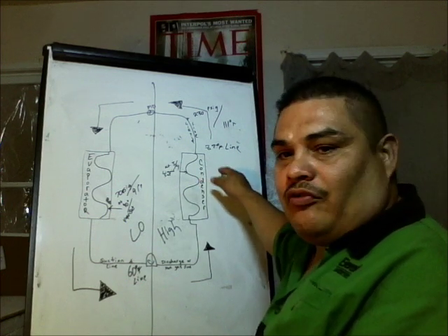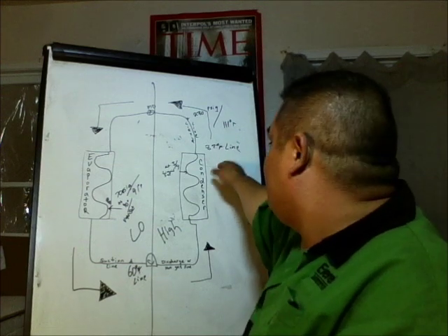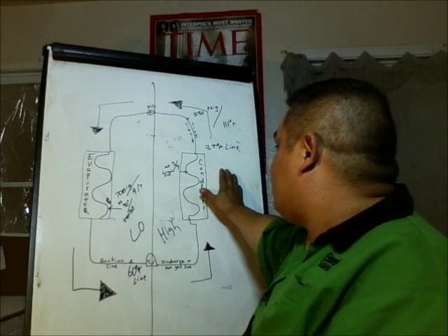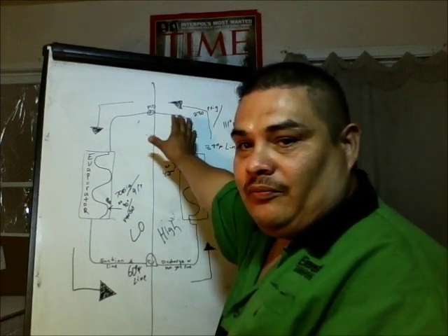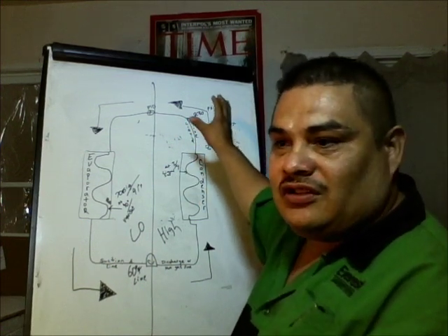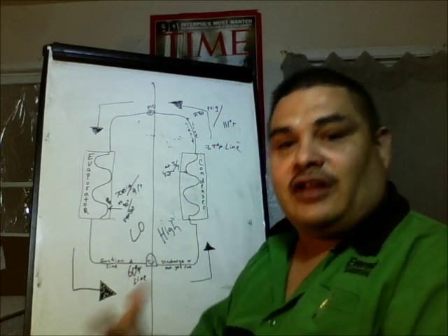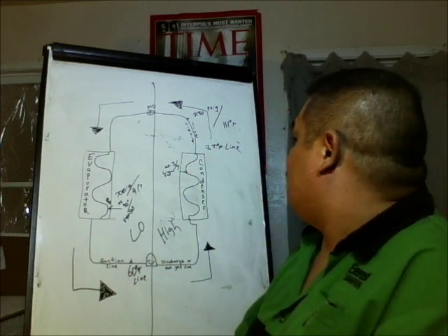You hit the point where it's complete liquid going out. That's a door where you're entering into subcooling. And that, again, is going out of latent heat and entering into sensible heat, where you can measure on the thermometer, and that's where we're going to measure subcooling.